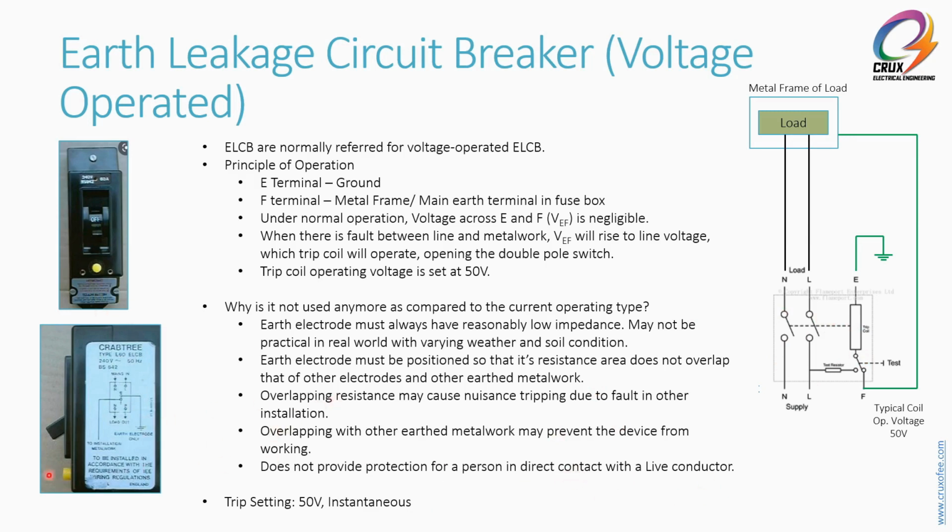If you can see here, there's a yellow button, which is the push button. When you press the test button, you are shorting from live to ground through some resistor. That resistor limits the build up to 50 volts, just enough to trigger the ELCB.